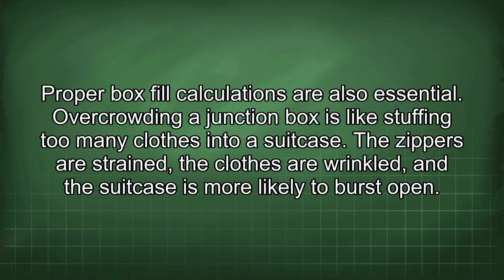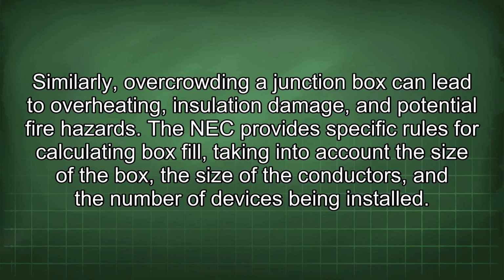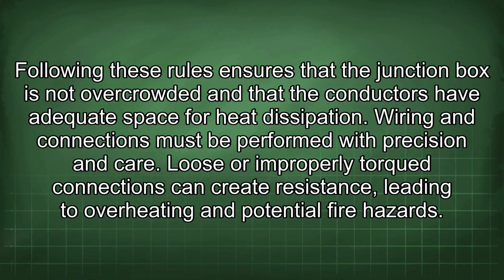Proper box fill calculations are also essential. Overcrowding a junction box is like stuffing too many clothes into a suitcase. The zippers are strained, the clothes are wrinkled, and the suitcase is more likely to burst open. Similarly, overcrowding a junction box can lead to overheating, insulation damage, and potential fire hazards. The NEC provides specific rules for calculating box fill, taking into account the size of the box, the size of the conductors, and the number of devices being installed.